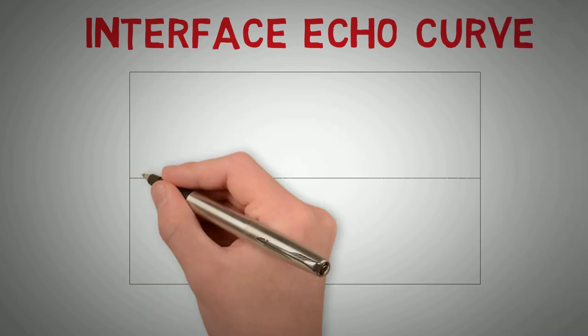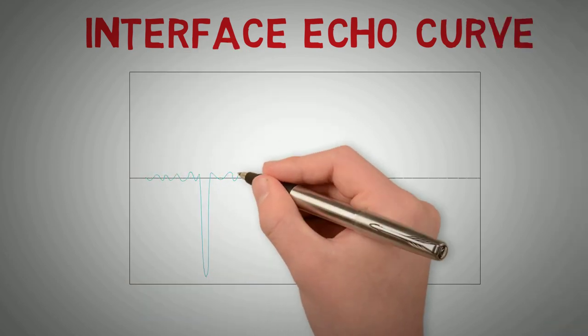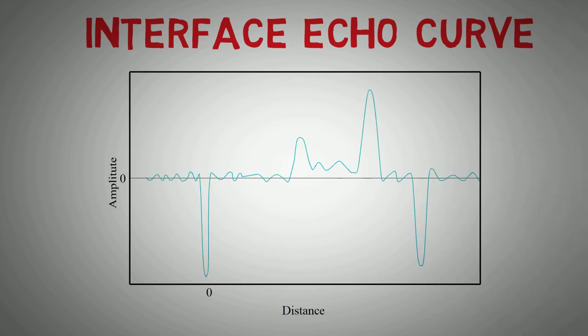Let us now look at the echo curve for an interface level, as our earlier example of oil and water in a vessel. Here we can see the reflection as the electromagnetic waves traveling down the probe encounter the surface level of the lighter oil. The remaining waves travel through the oil level and are reflected from the water and oil interface. We can see a larger amplitude reflection in the echo curve as a result of its denser properties.